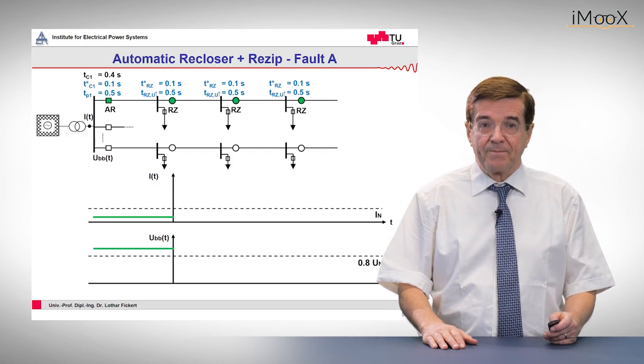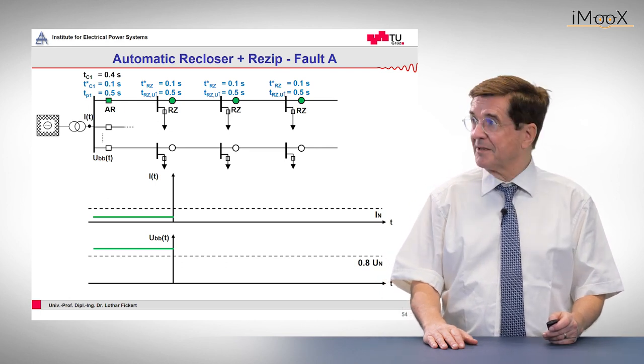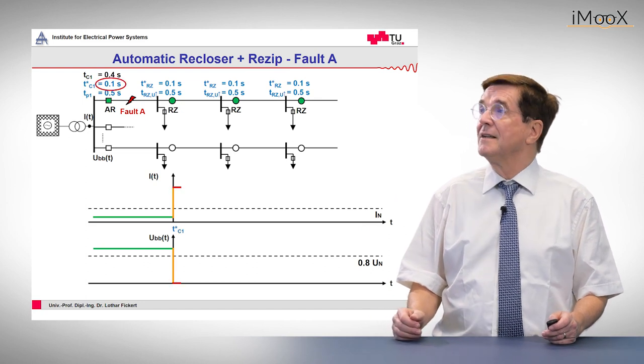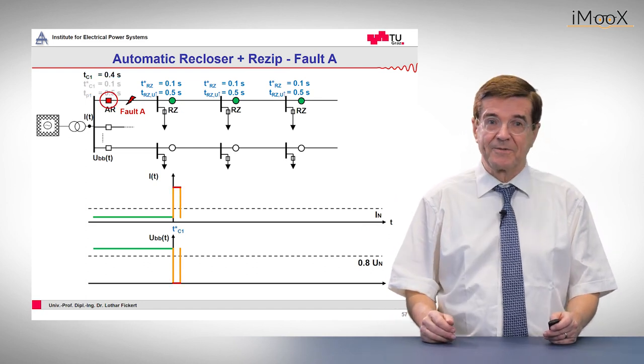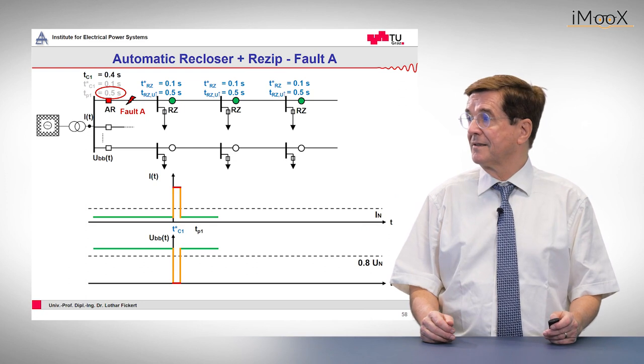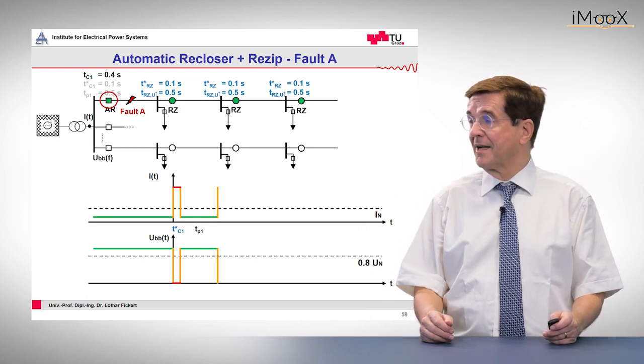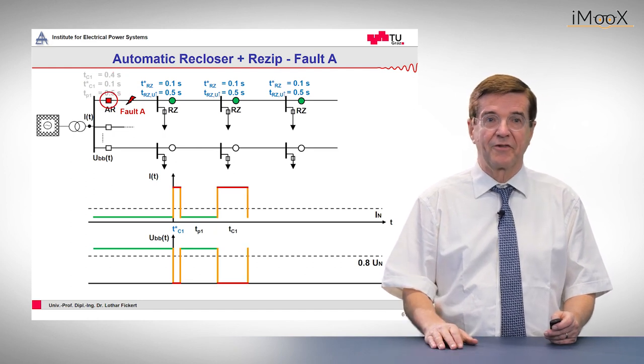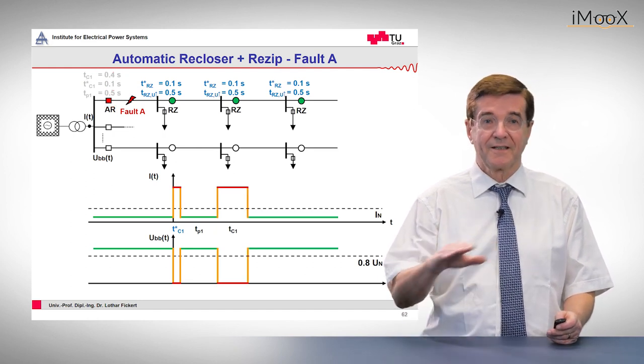Now for the beginning, the fault at the beginning of the line, we have a very similar occurrence. So the fault comes up, the first auto recloser trips immediately, and after its recloser time it recloses on the fault and trips out with a definite fault. And again, this was it.